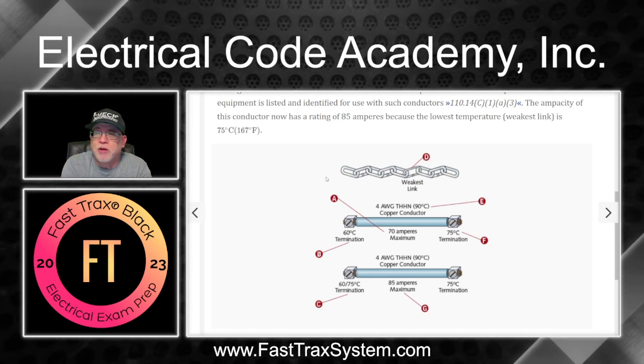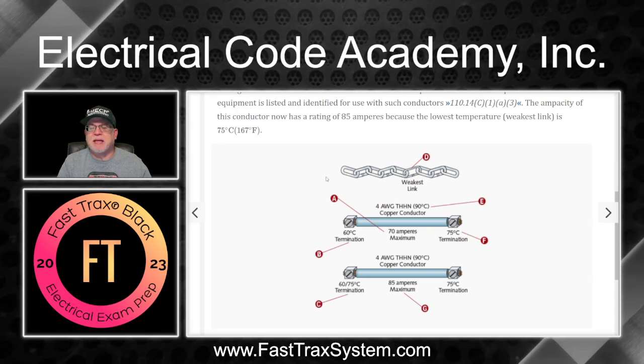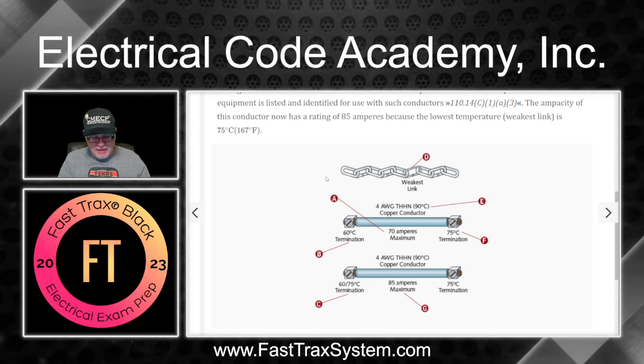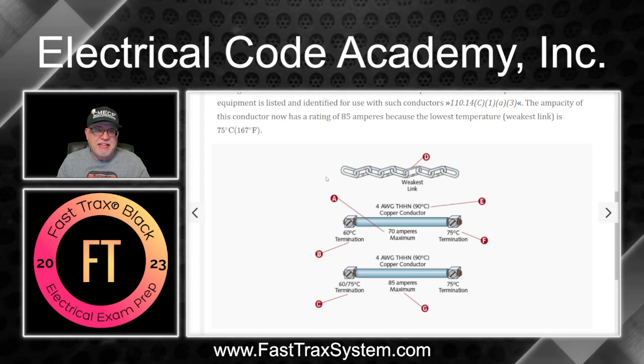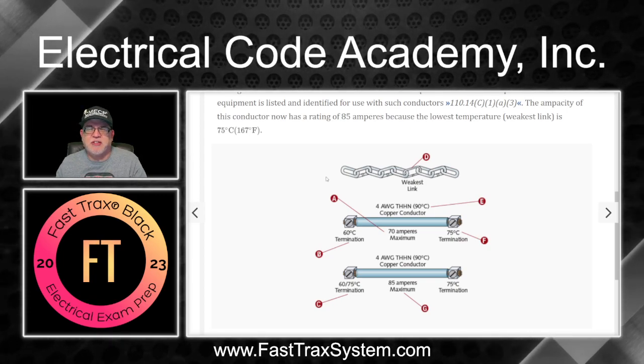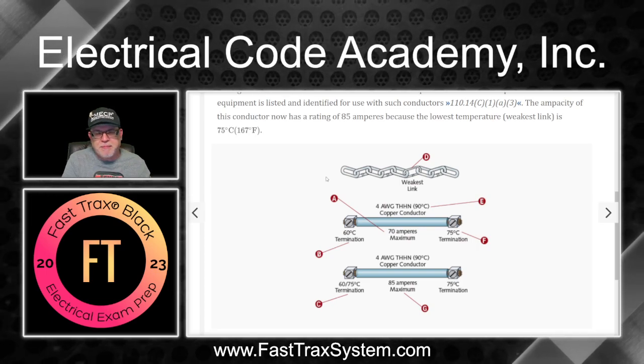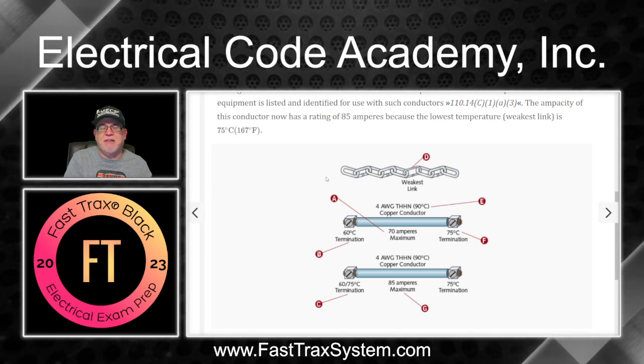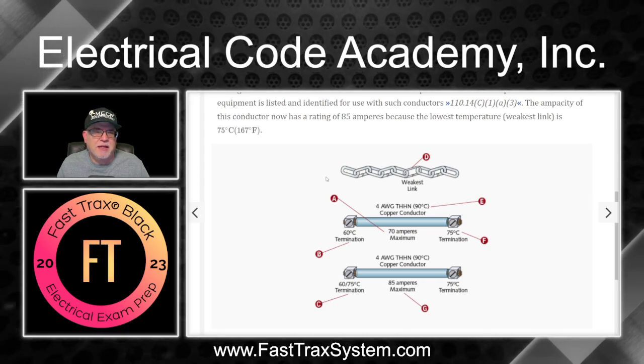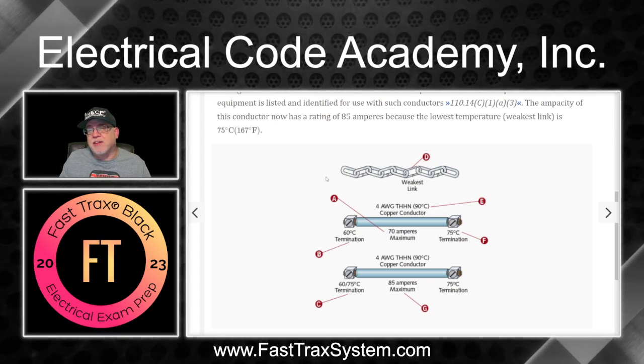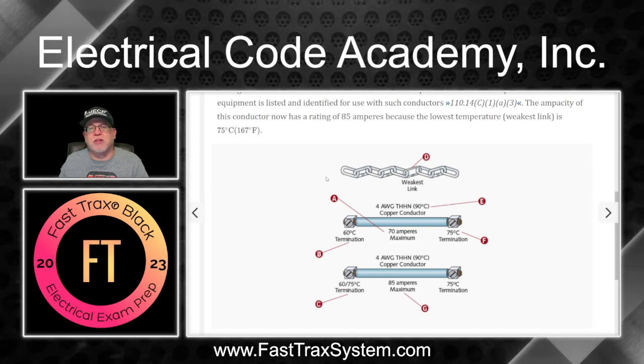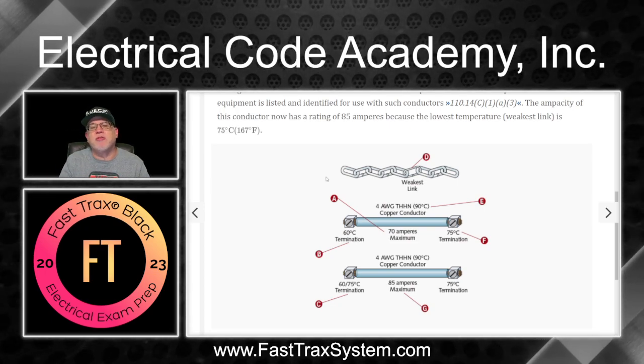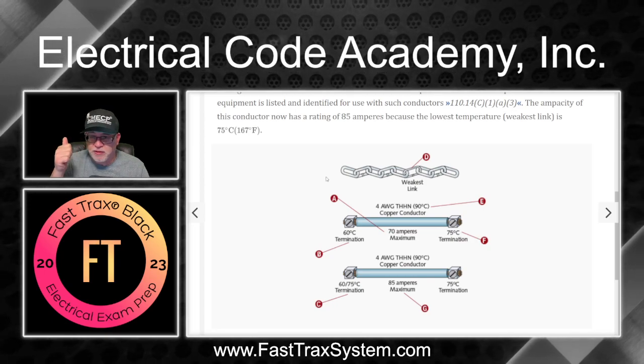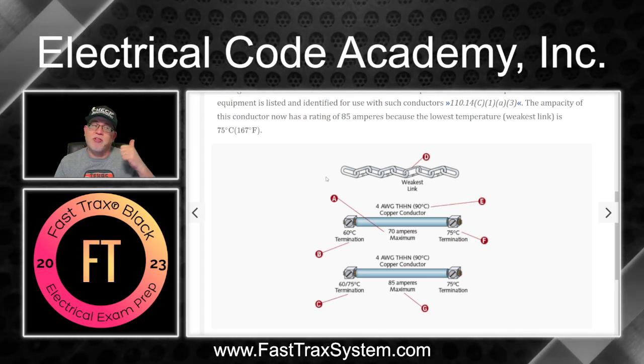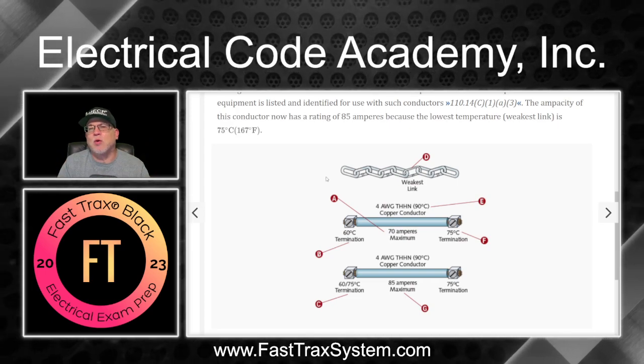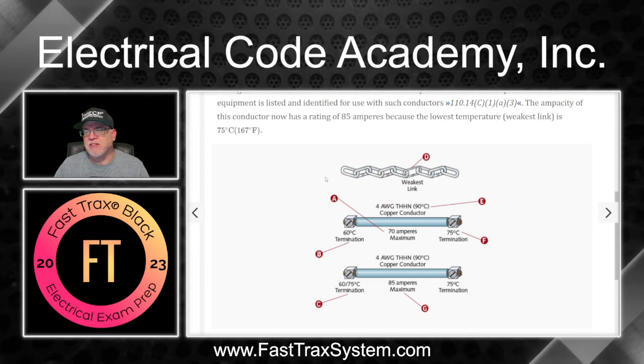That's important to remember, because you could have applications where a device might be rated 60 degree C terminations. The lugs on a breaker might be 75, and the wire might even be 90. But the weakest component here is the termination onto the device, which was only 60. So thus you can't exceed the 60 degree. Even if your insulation is higher and the terminal on the supply end is rated higher, that's the weakest link concept, okay?